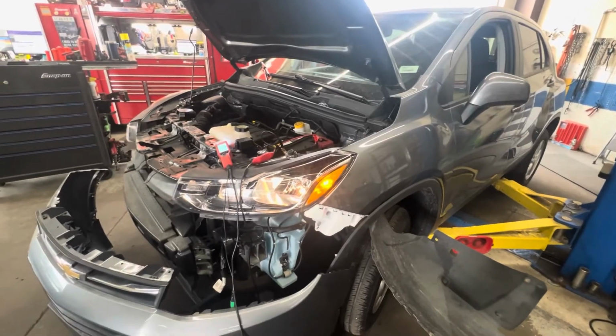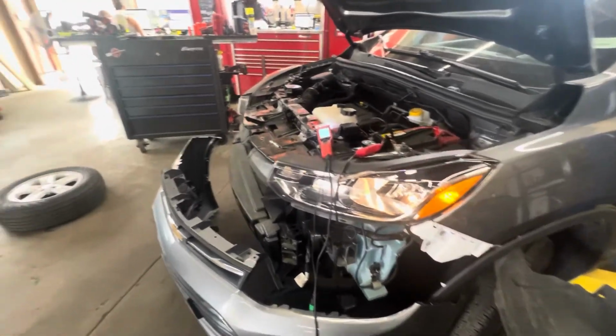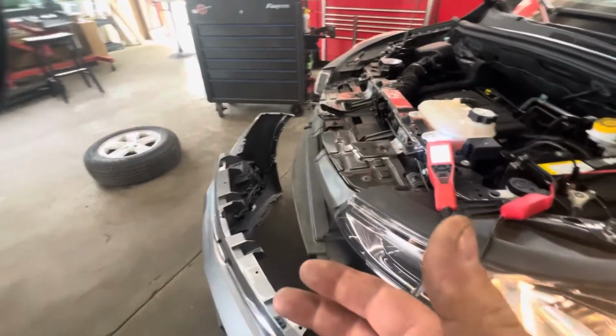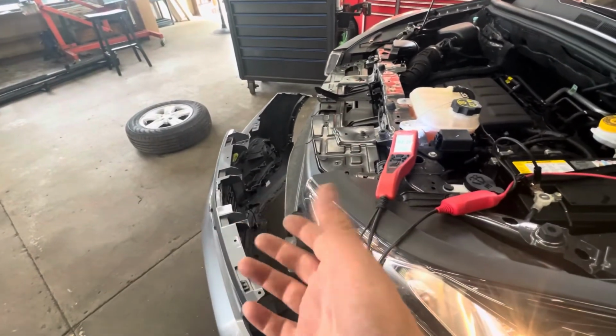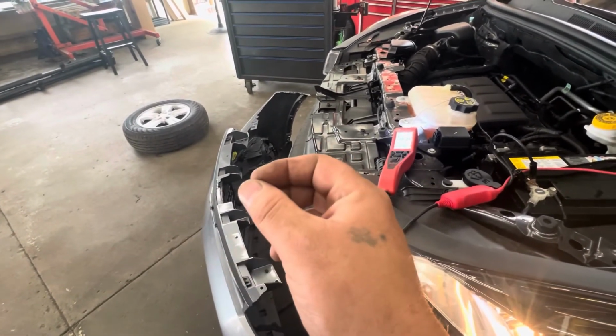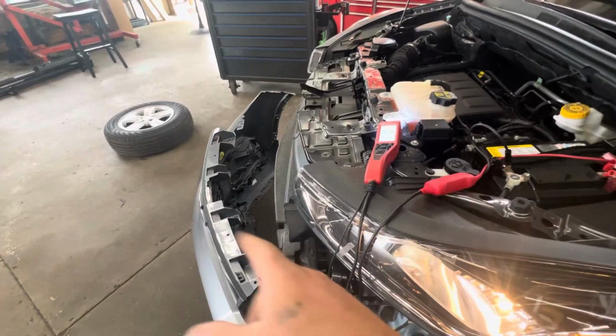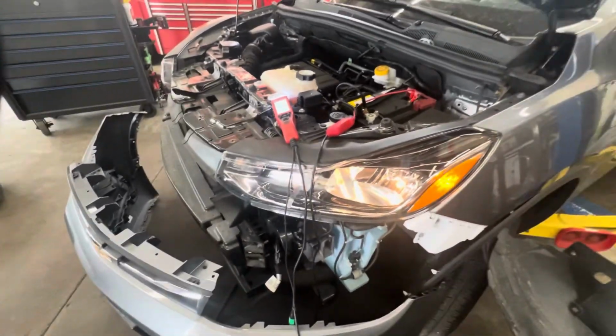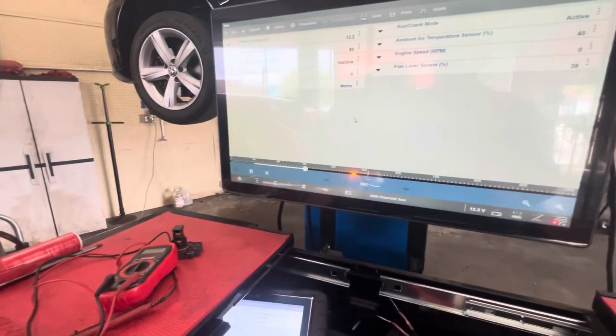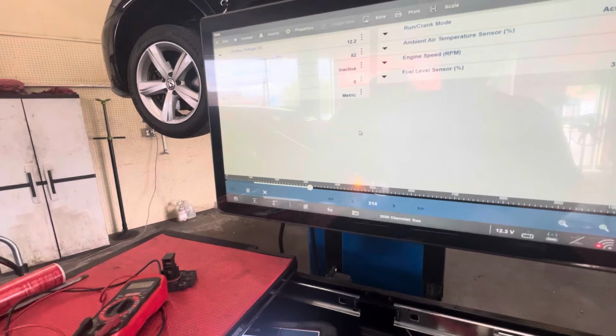Hopefully this will help somebody, because I would assume even if you do have a bad ambient air temperature sensor, you're still going to need to do this reset after you change it, because it calibrates. If it calibrates a bad value in there, like this one had negative 31, you have to reset it.